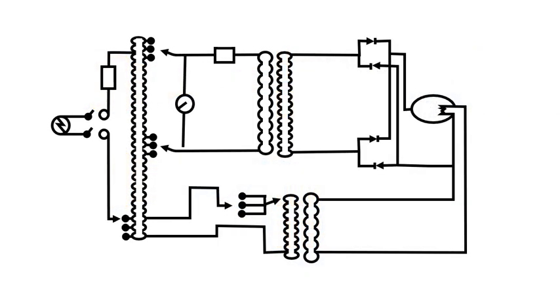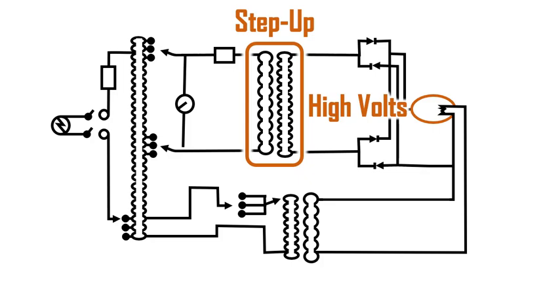Different parts of the X-ray circuit need different volts and amps. The X-ray tube itself needs very high voltage to make X-rays, so that part of the X-ray circuit uses a step-up transformer to increase the voltage.